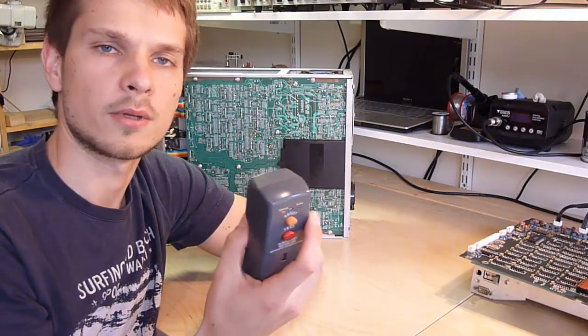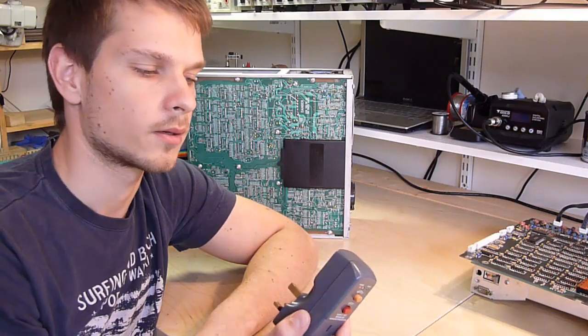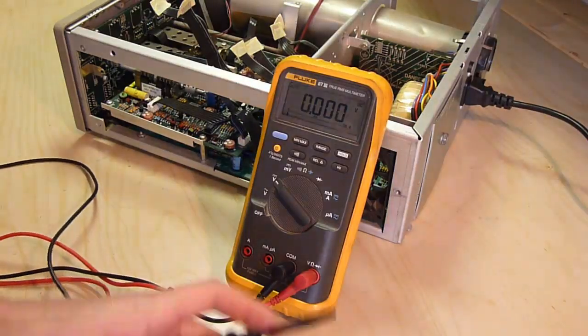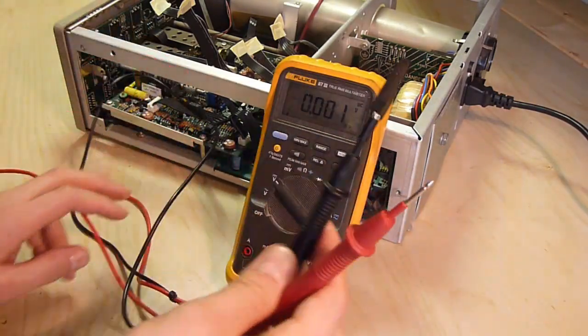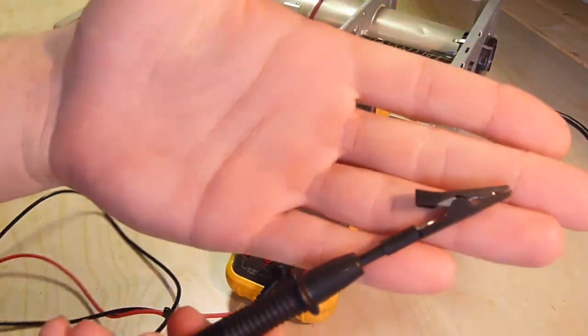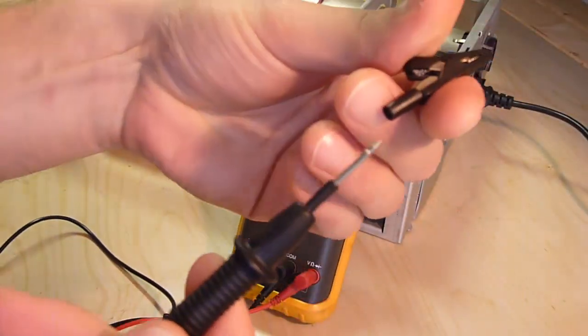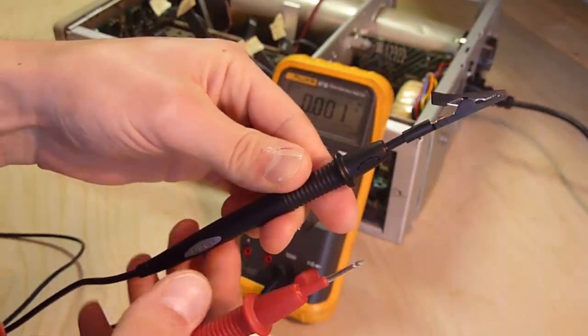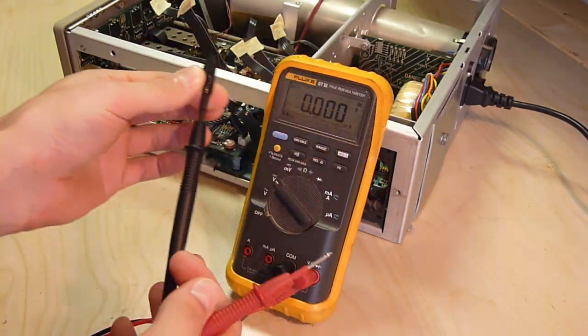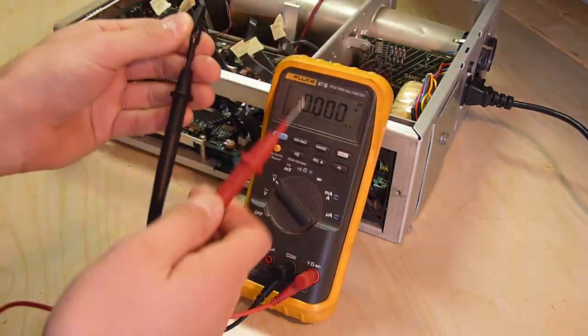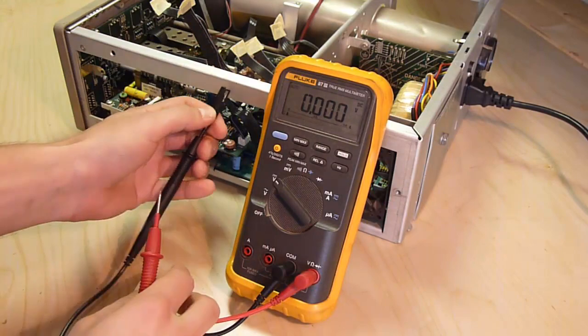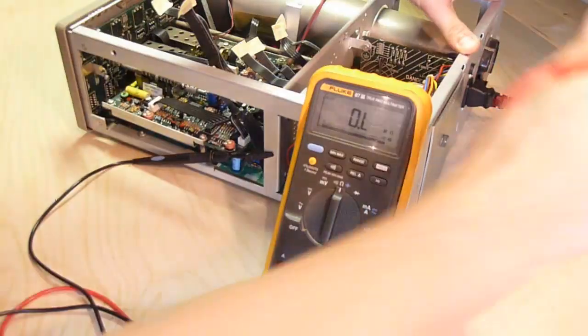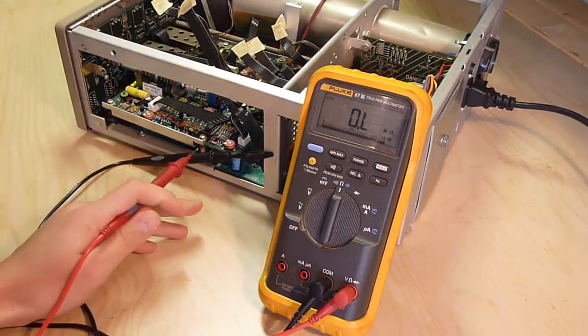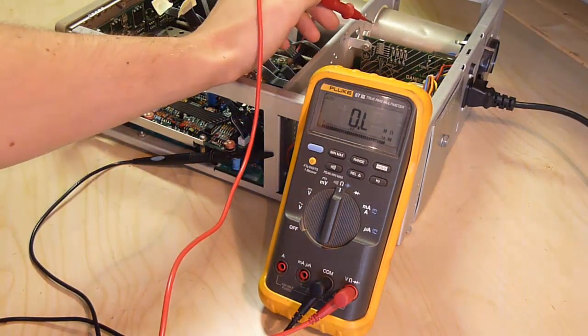So although this will not save your life in all the circumstances, it's an extra layer of protection. Okay, so what I have here is a Fluke 87. We have these two probes and one of these little clips which you can just slide onto a probe. And this is handy, as I mentioned, if you only want to use one hand to probe, you attach this to some suitable ground point, and then you can just use one hand and keep the other one behind your back. So I'll just attach this to the chassis, and the first thing I want to measure is the voltage on the filter capacitor on the main board.